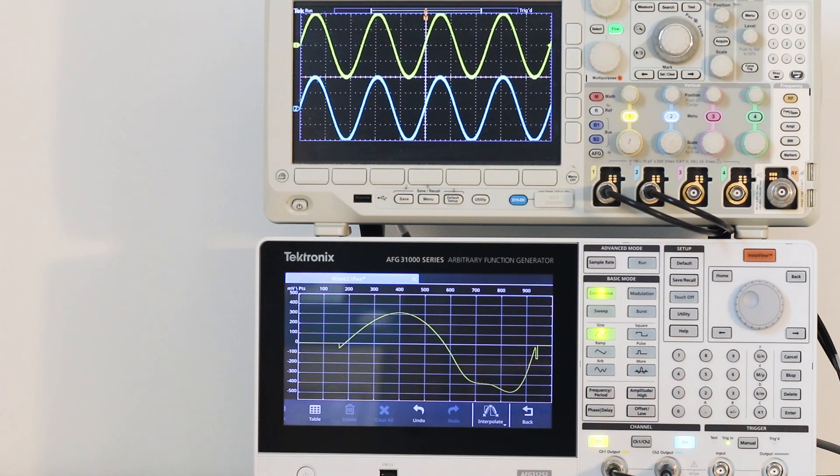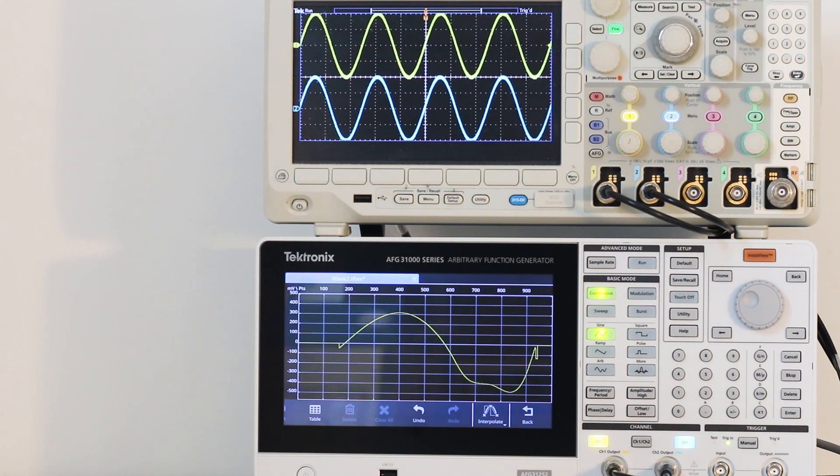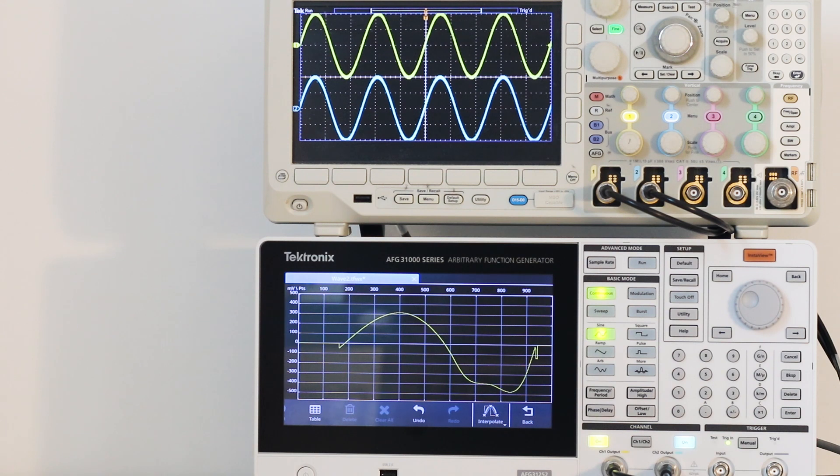This arbitrary waveform can be saved in the AFG, in the oscilloscope, or in a flash drive that is inserted into the USB slot in either instrument.